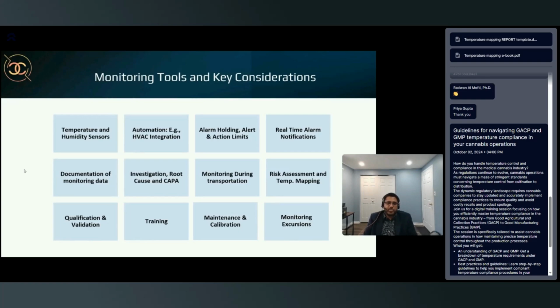If that certificate is traceable to NIST standards, that's well above and beyond, and that might be more applicable also on the GMP requirements. And then also, I would suggest not to go with paper monitoring. Like, you're not going to your sensors every morning and evening and writing your readings, temperature and humidity, because it's a time-consuming step. And if you have a multiple-room facility, you will be spending a lot of time monitoring and analyzing that data and scanning that data, obviously.